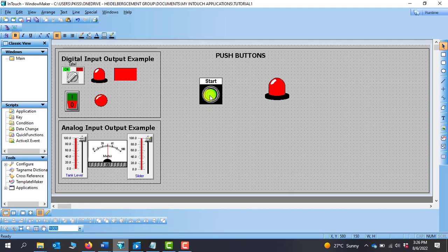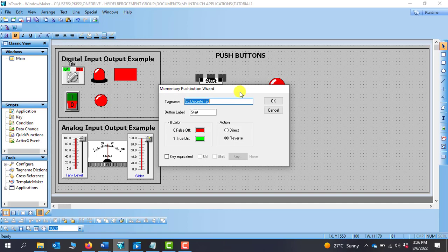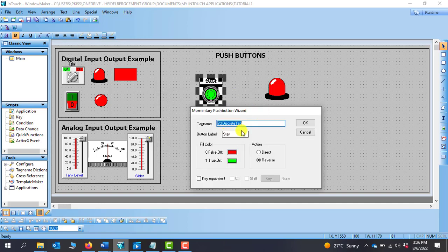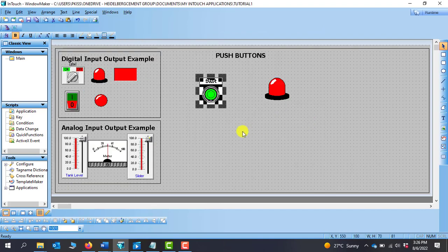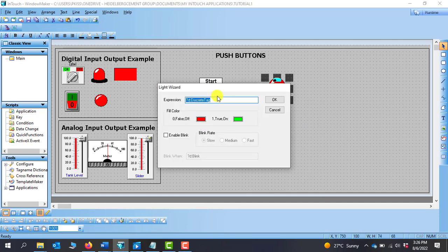The next thing to do: we need to assign tags to them. We double click and assign specific tags. We can create new tags — this can be B1 as button one. It asks me to define, I go to OK. The type — we know this is a digital switch, so we use memory discrete. I click save, close it, and click OK. I need to assign the same tag name to the lamp, so B1, and click OK.